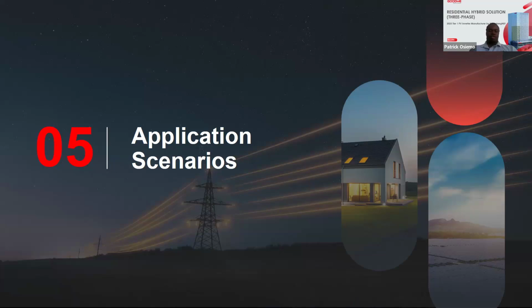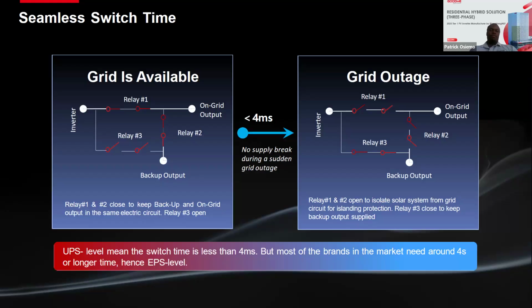Now, how do we apply these products to the residential hybrid systems? So first off, we have the seamless switch time. Most of the African countries do not really have a stable grid. But we do know that homes would not like to have any power interruptions, for comfort purposes, security purposes, and the likes. So with the ETLV, we have a very fast, seamless switch time, which is less than 4 milliseconds. This is above par compared to what we have in the market right now with other brands. Most brands are above 10 or above 20 milliseconds. We are very fast, less than 4 milliseconds, and your home will not even sense that the grid has a failure or a blackout of such kind. So very fast, seamless switch time, under 4 milliseconds.